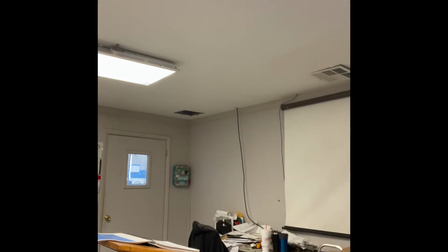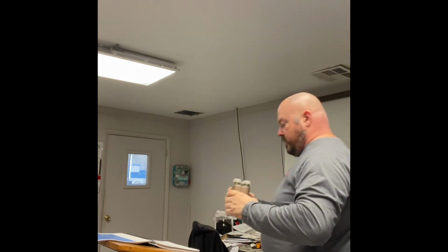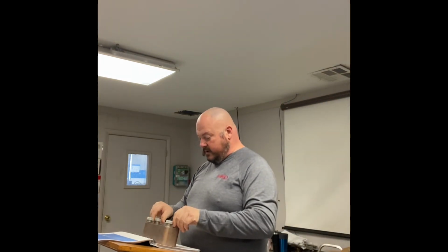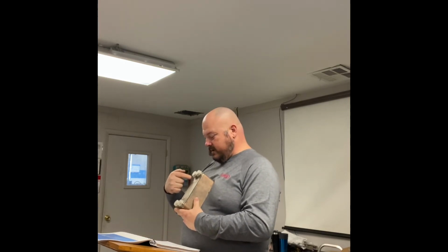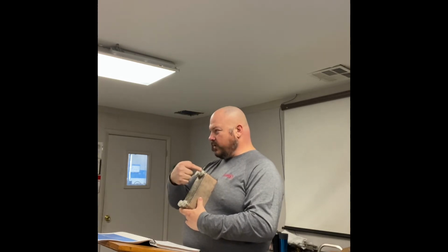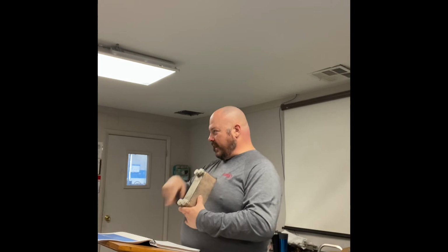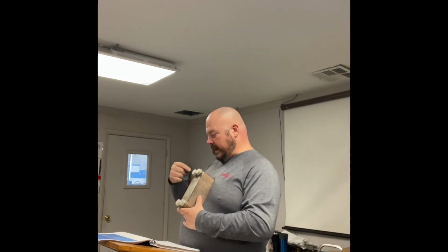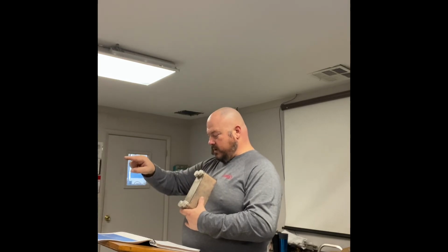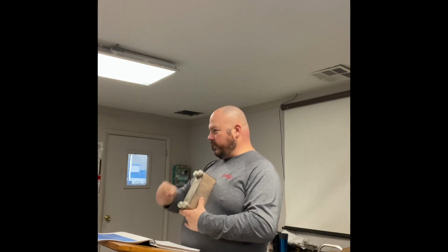In a lot of refrigeration systems, instead of air cooled, they're liquid cooled. So they have a counterflow heat exchanger. Let's see here, I've got one right here. Counterflow heat exchanger. Okay, so you've got an in and an out for refrigerant and water. In English, water goes in one side, comes out the other. Refrigerant goes in one side, comes out the other. They go in opposite directions of each other. Cold water, hot water, hot refrigerant, cold refrigerant. Okay?